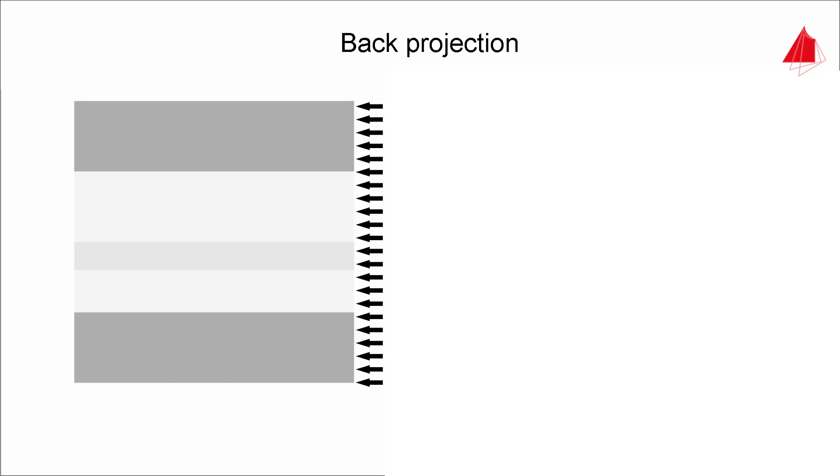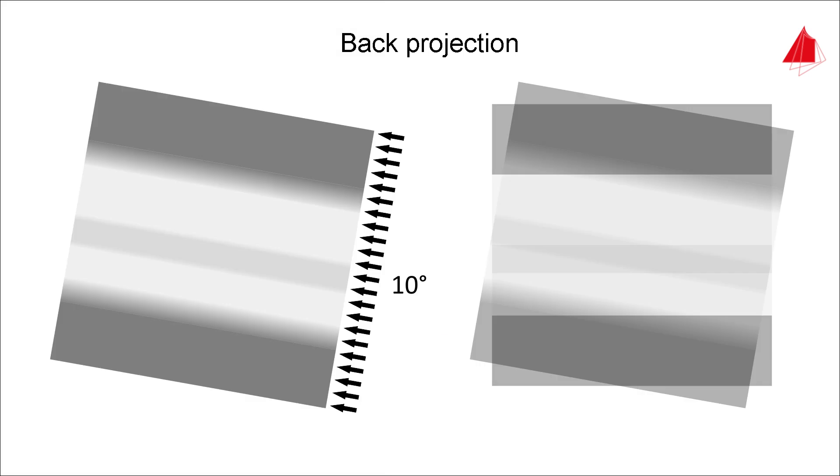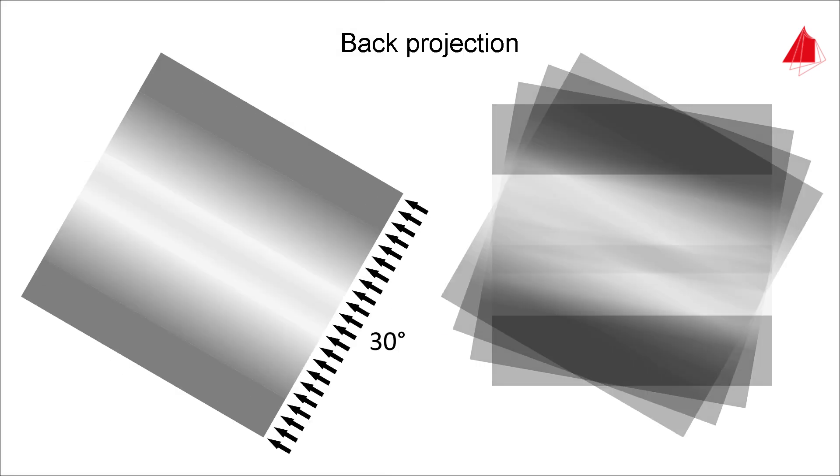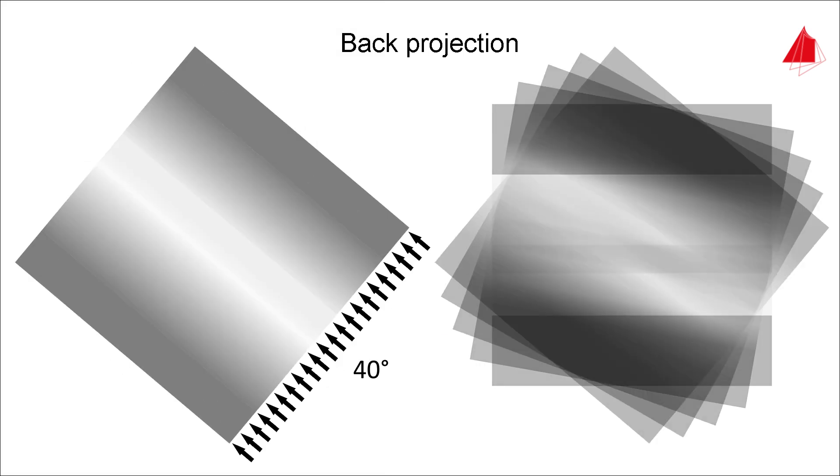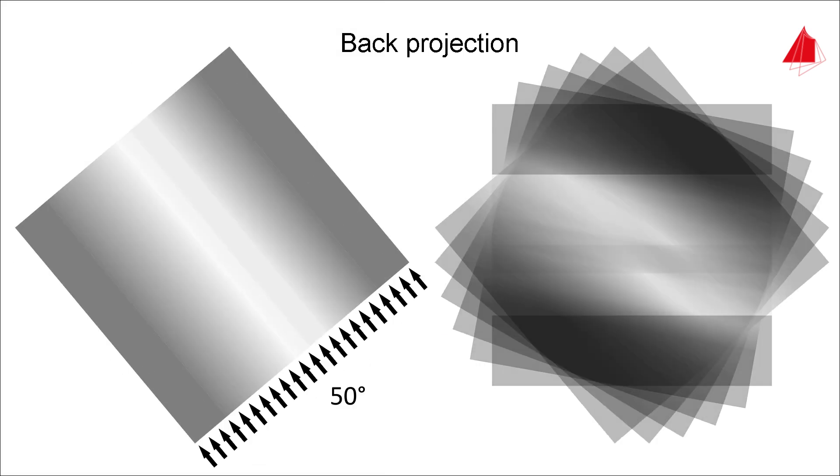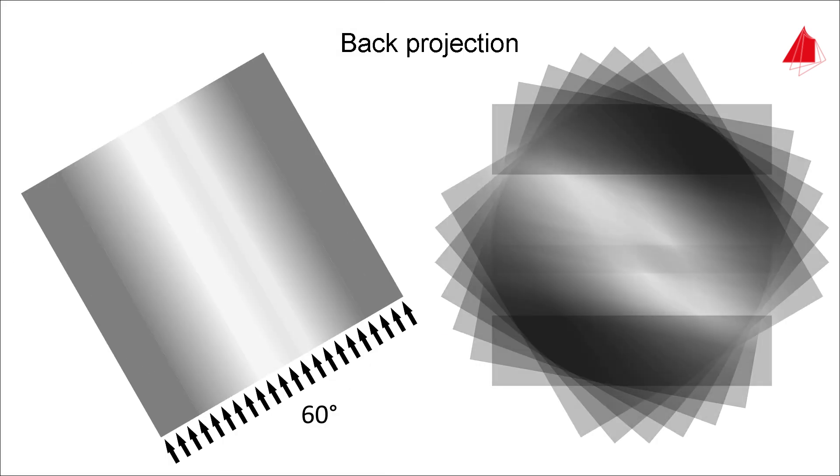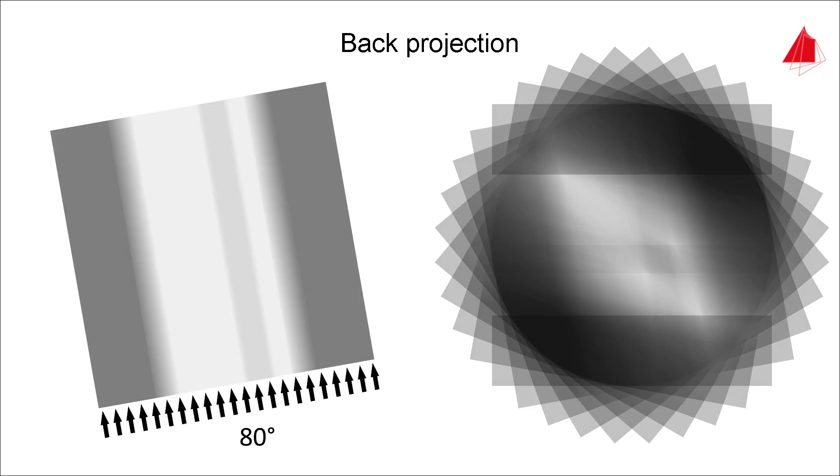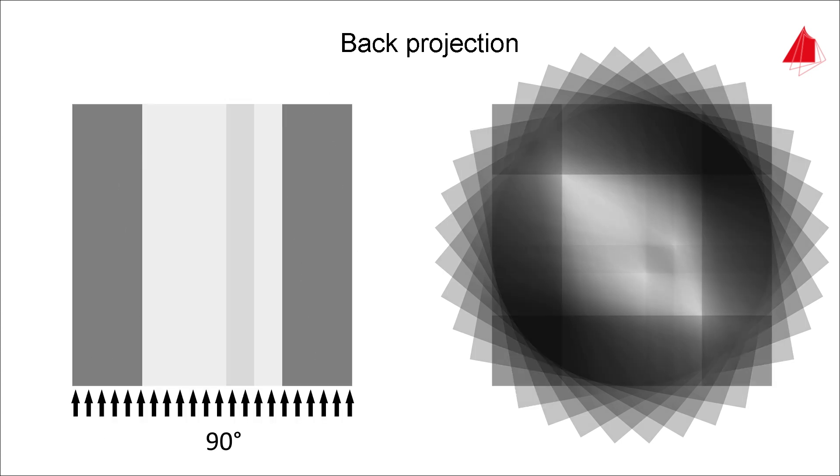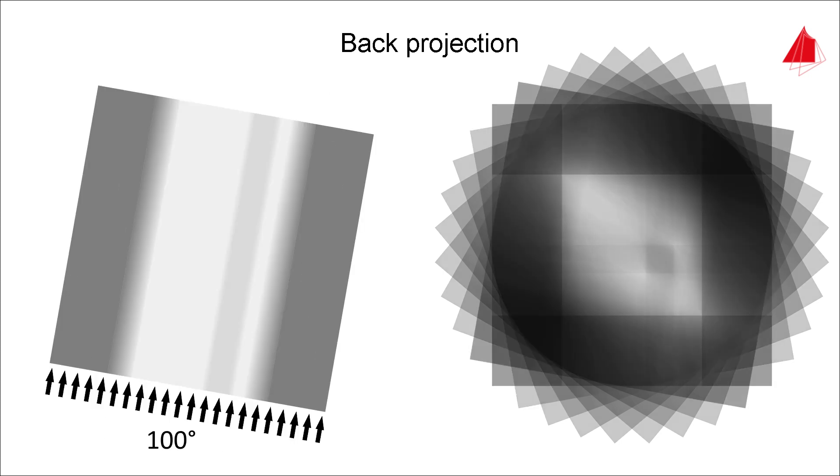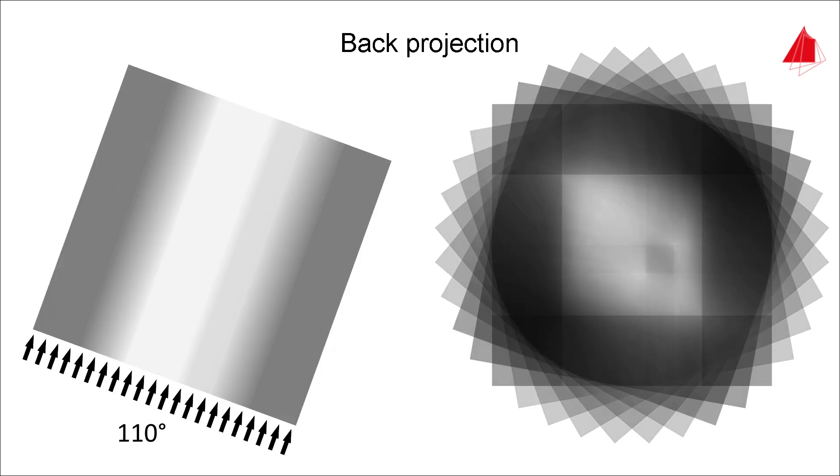After having taken all x-ray images, the distribution of the transmitted x-radiation is projected back into the sectional plane. This process is repeated for each x-ray image and the distributions are superimposed. With each superposition, the quality of the model increases.